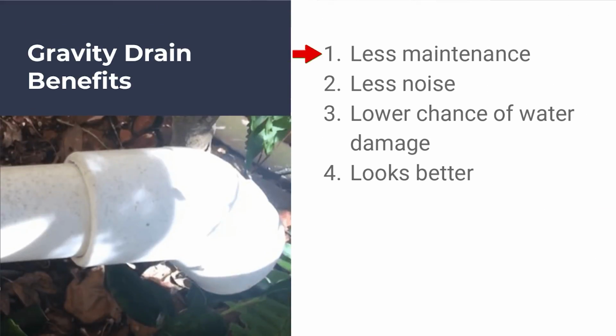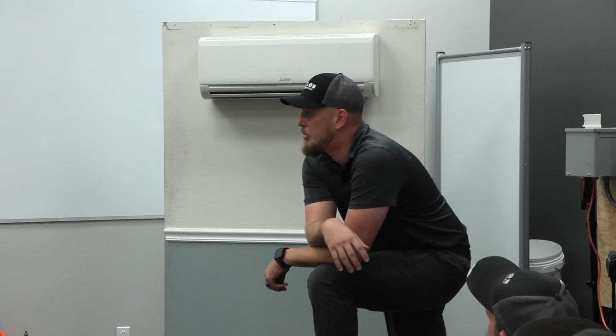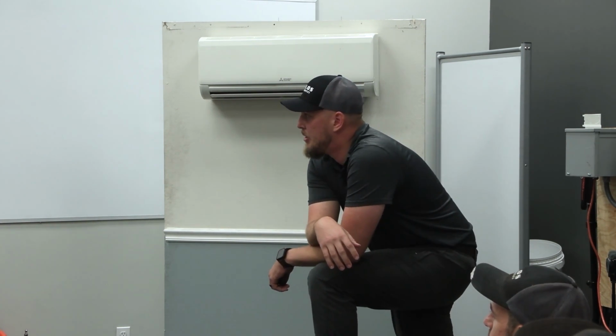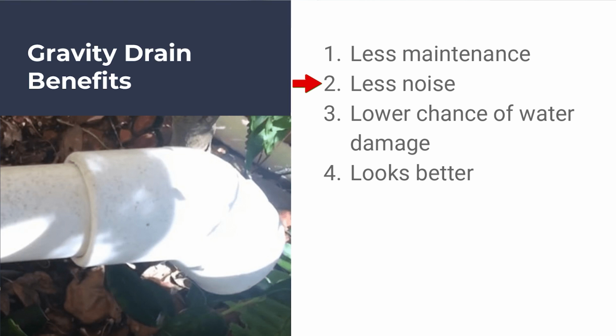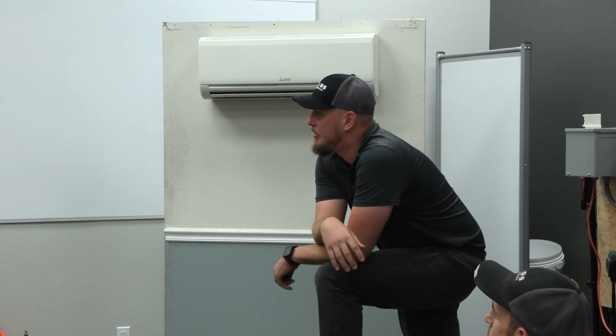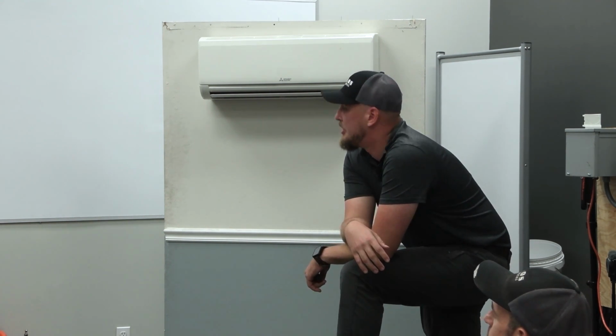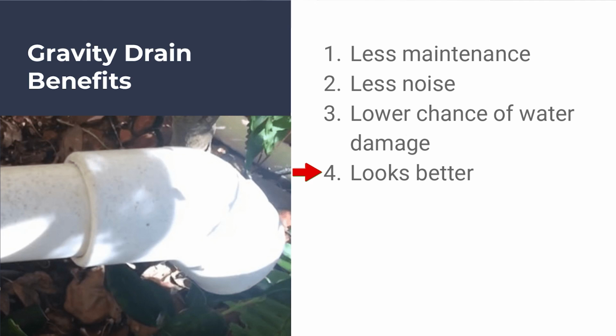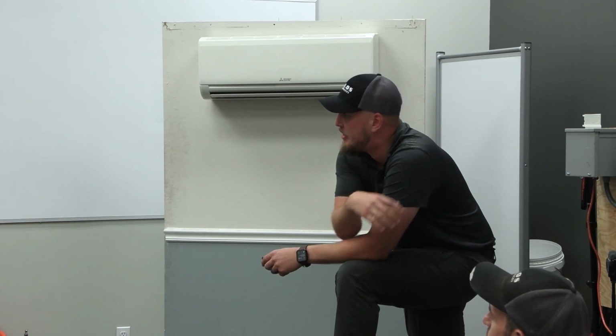So the gravity drain benefits: we have less maintenance. We're no longer talking about a small reservoir that gets filled up with gunk. We're talking about a 3/4 inch pipe that's draining outside, so less maintenance is needed on those. Less noise for obvious reasons. There's no pumps running on a gravity drain. Lower chance of water damage. These units are installed at various locations, often above electronics, furniture, hardwood floors. So when you don't have a chance of a pump failing, then there's less chance of water spillage. And they just generally look better. This unit here is installed with a gravity drain, so you don't have any additional line height on it. You don't have a pump underneath the unit, so just for the aesthetic of it, it looks a lot better. So that's for the gravity drains there.